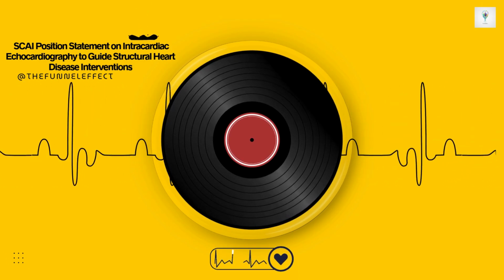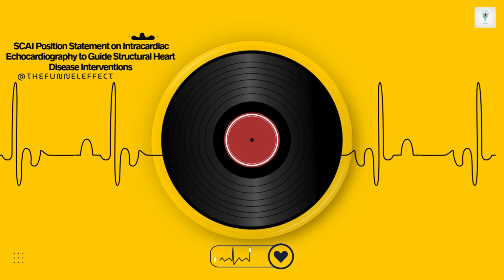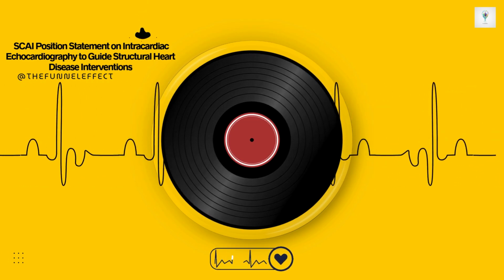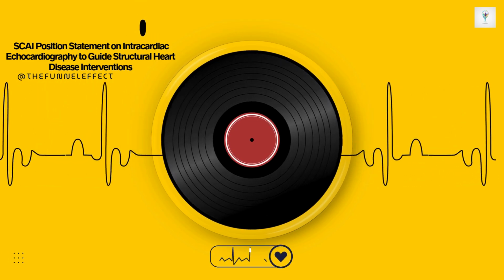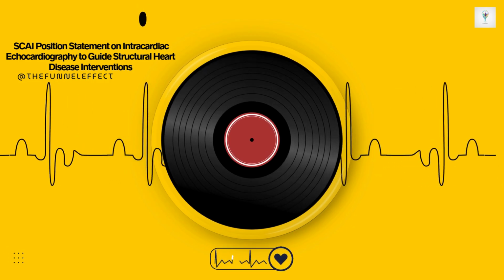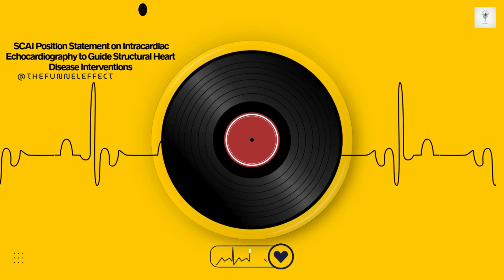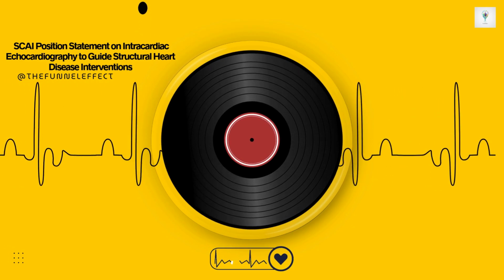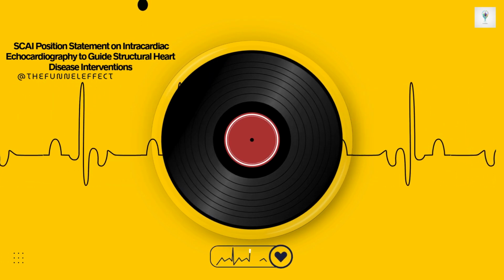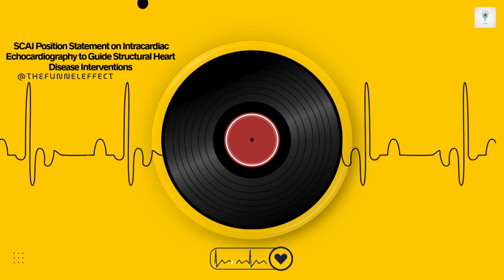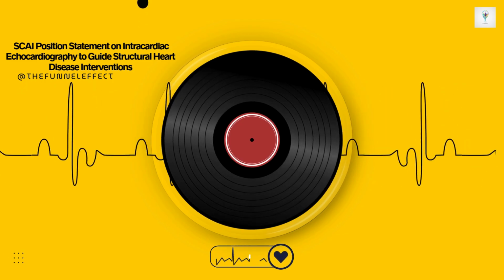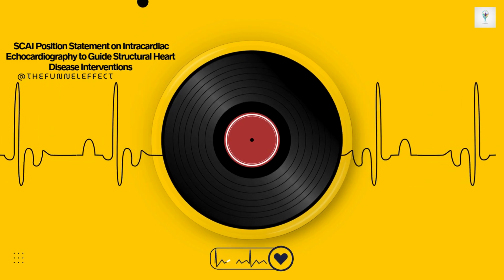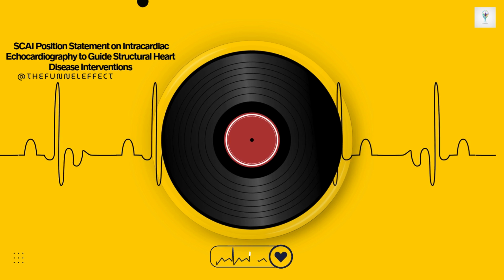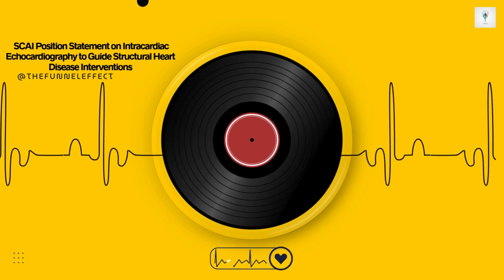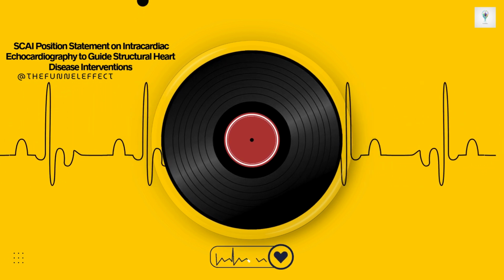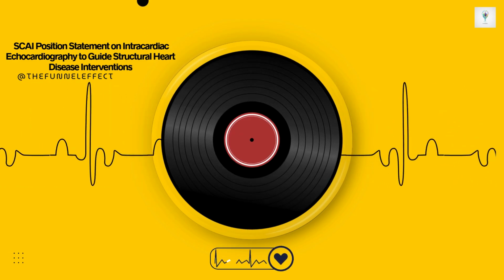NuVision and Verisight Pro. The NuVision, the 10 French one, features independent distal tip rotation, so the very end of the catheter can be steered separately. That mechanical flexibility is really helpful for navigating tricky anatomy and getting just the right image plane without having to twist the whole catheter shaft. And the Verisight Pro, the smallest at 9 French, uses digital 2D steering. So instead of mechanically moving the tip as much, you can electronically steer the imaging plane within the 3D volume that's already been acquired, which gives you real-time flexibility.